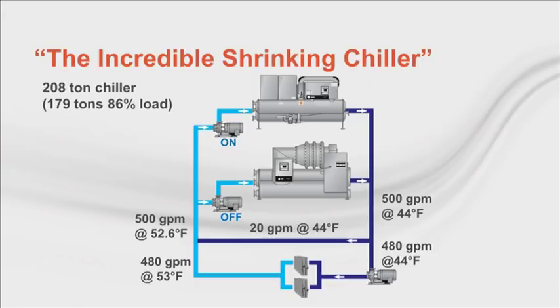As in our last example, each chiller's capacity is fully defined by the flow times chiller DeltaT. As the return temperature falls, the chiller unloads to meet set point, and we just lost an extra 10% of the chiller capacity. In a little while, the second chiller will be staged on, and the surplus water will depress our chiller return water temperature even further. If you only get 90% of your design building DeltaT, you'll only get 90% of your installed chiller capacity.